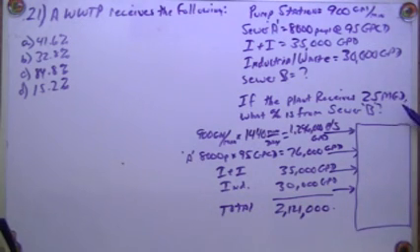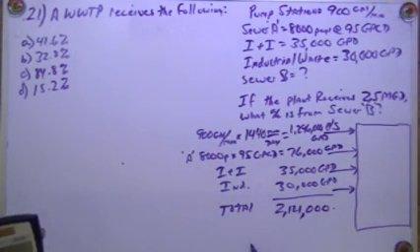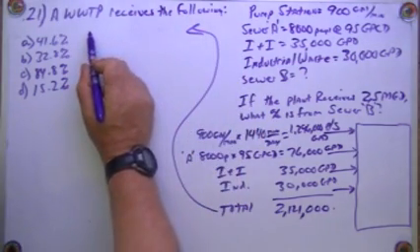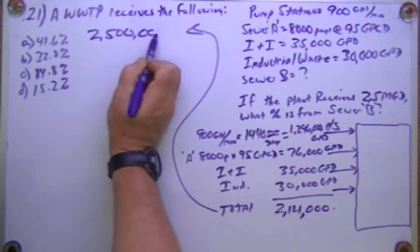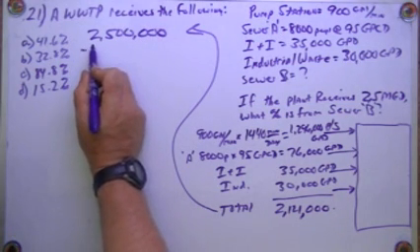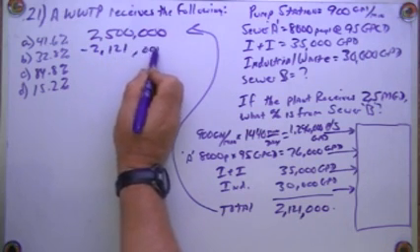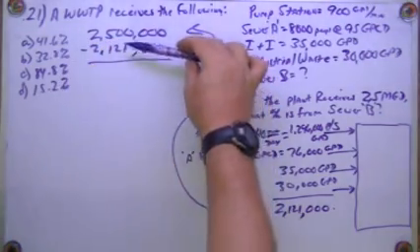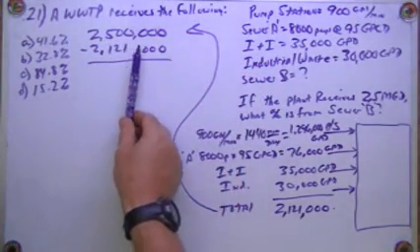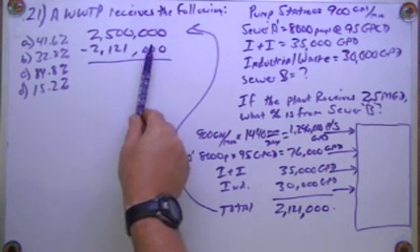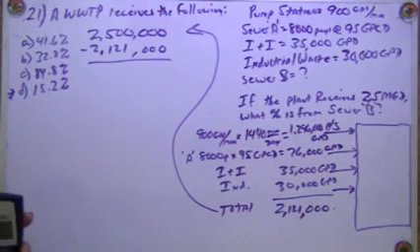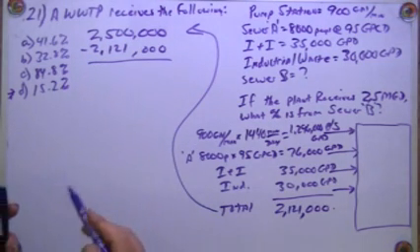So if the plant receives 2.5 MGD, I'm going to come back up so it'll be easier to see. 2,500,000 minus 2,121,000, so that's pretty close. It's almost 80-85% of the top number, so what's remaining is less than 15% give or take. So what the industrial waste from Sewer B is, is probably going to be 15%. But let's keep going and we want to do that to make sure we don't fat-finger the calculator and do something stupid.